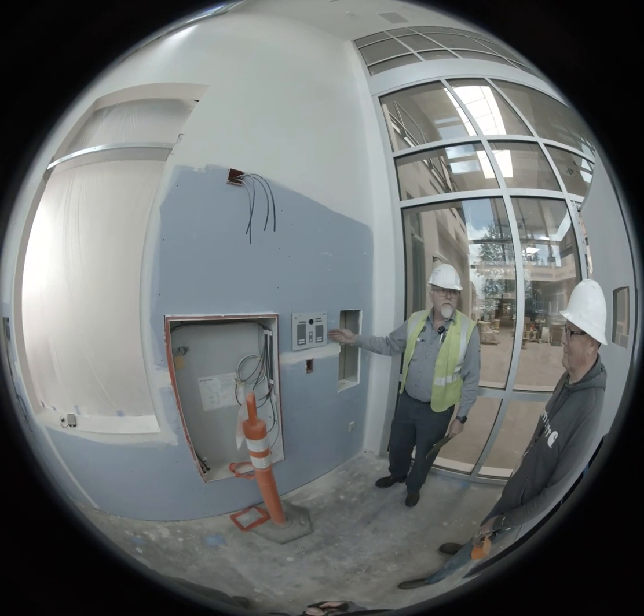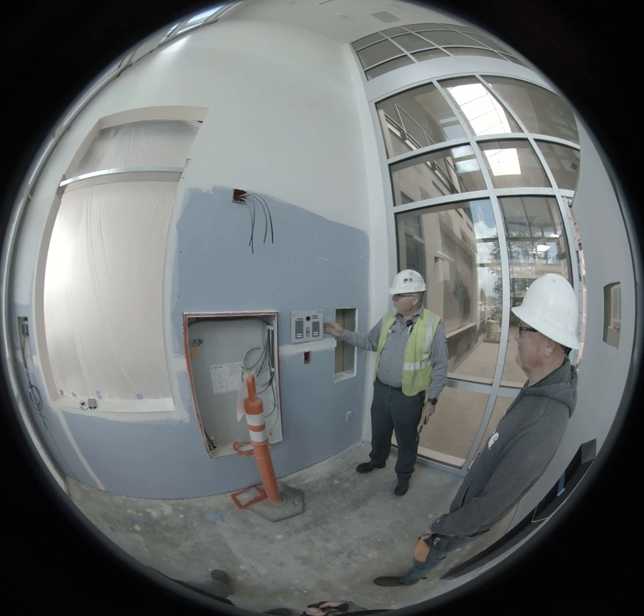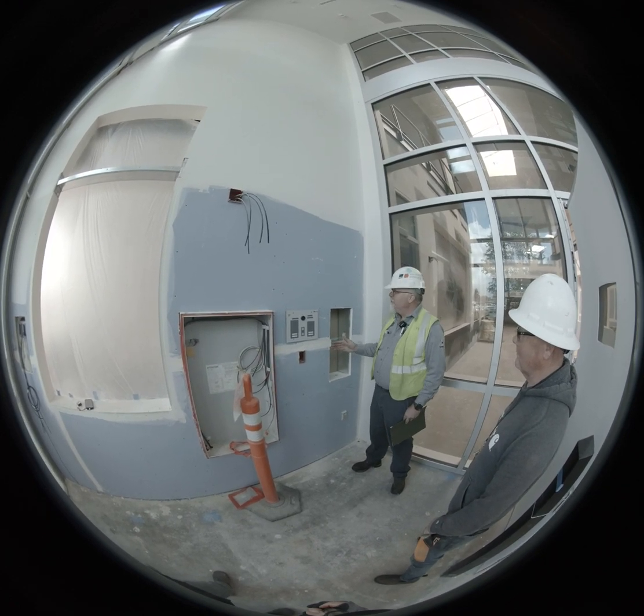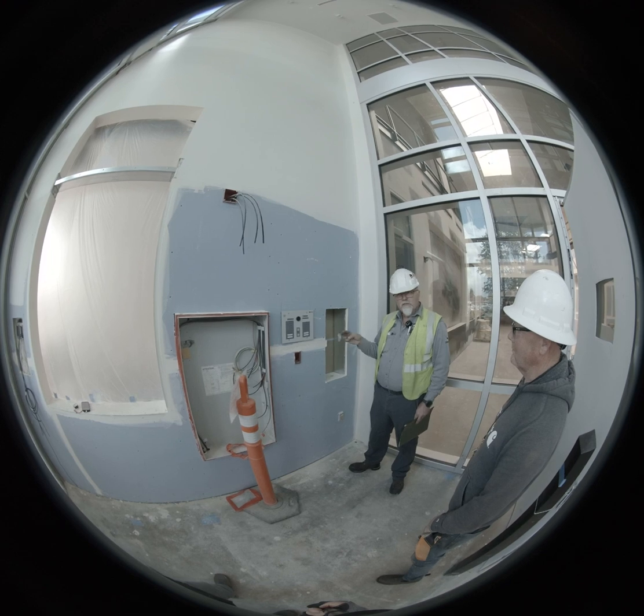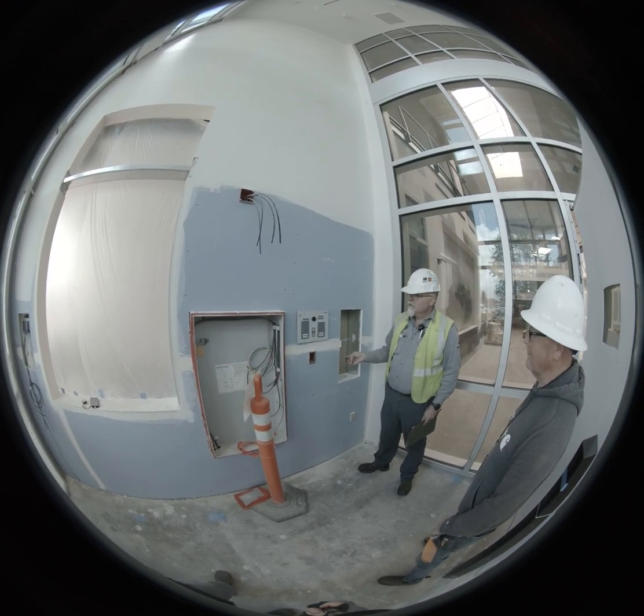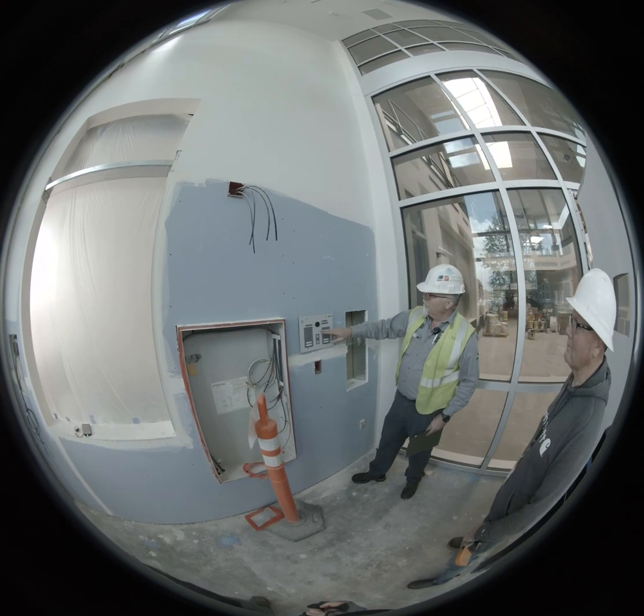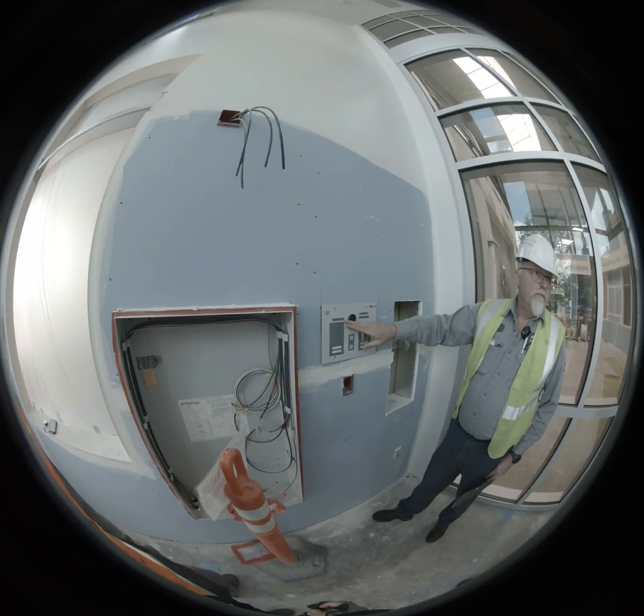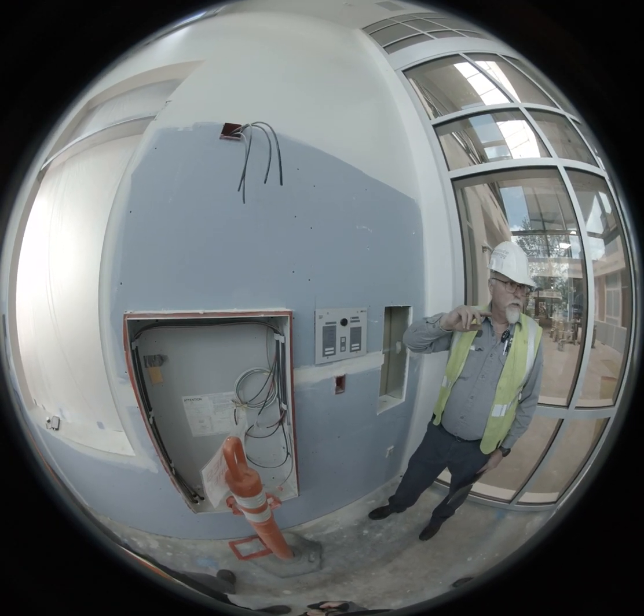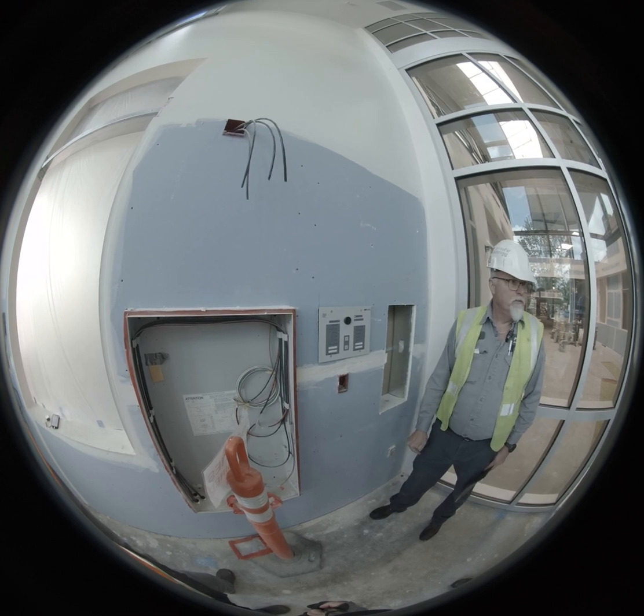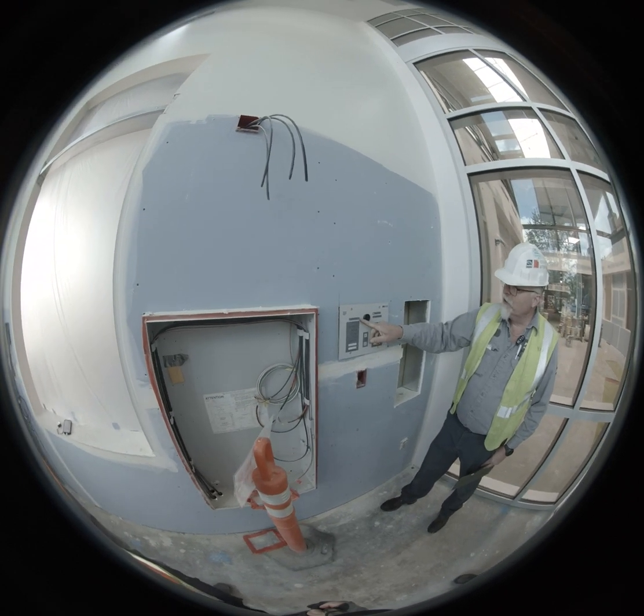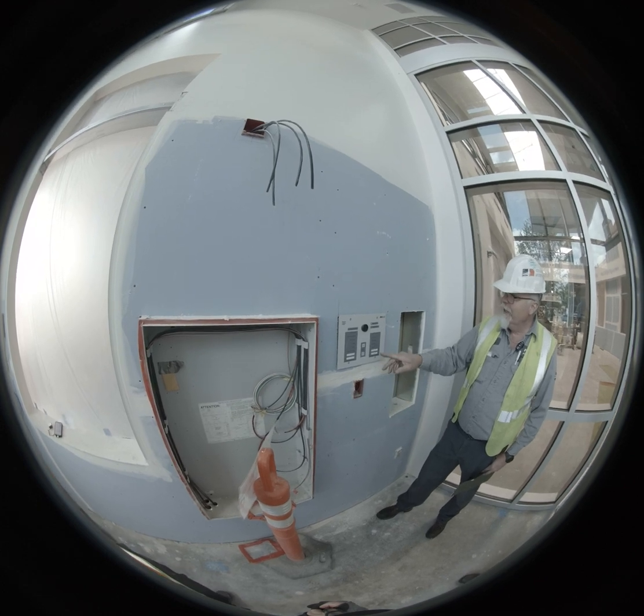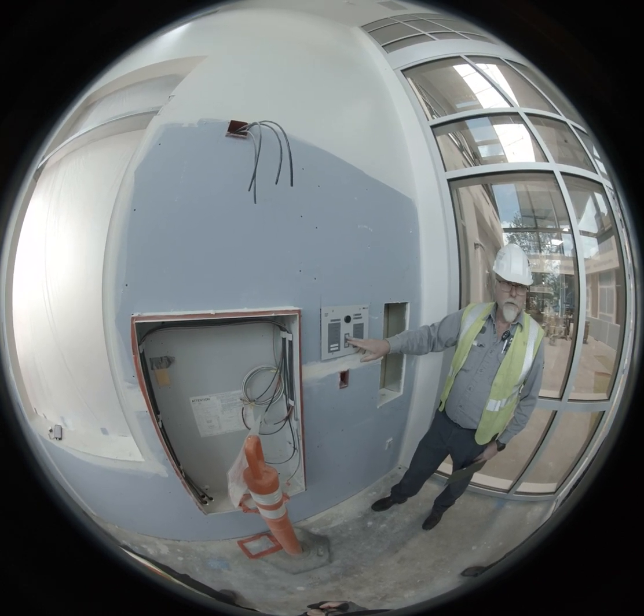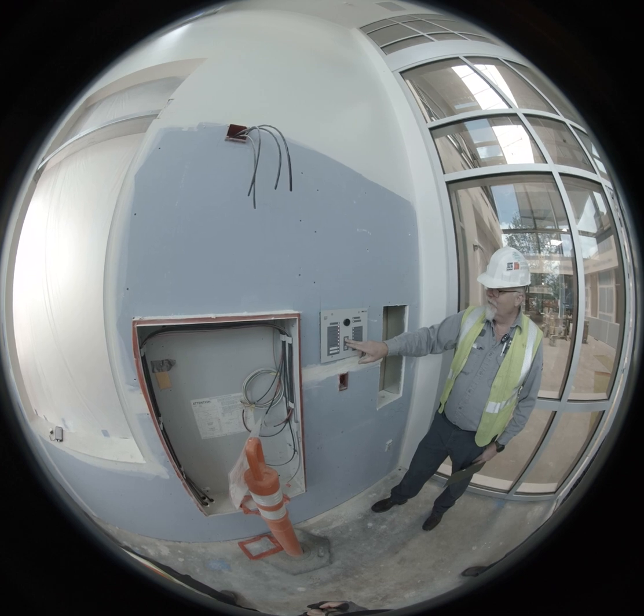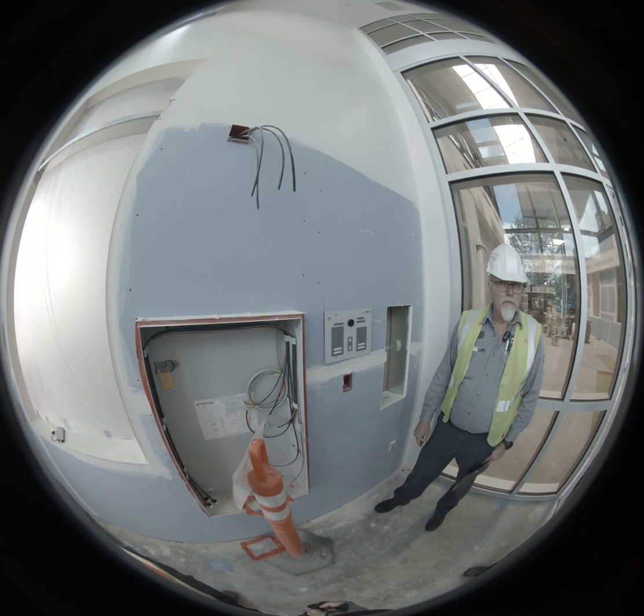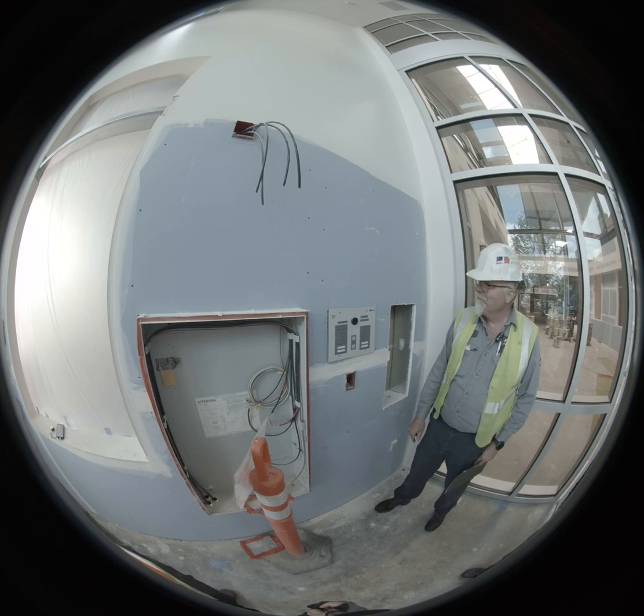Okay, right here we have the remote serial annunciator. What this panel does is mimic what the generator is doing as far as the faults. Switch not auto simply means that the switch on the generator set is in any position but the automatic position. It will come up and give you a visual light as well as an alarm. I'm going to push this here and it's going to get a little noisy. You'll have that alarm. I think people might be able to hear that one.